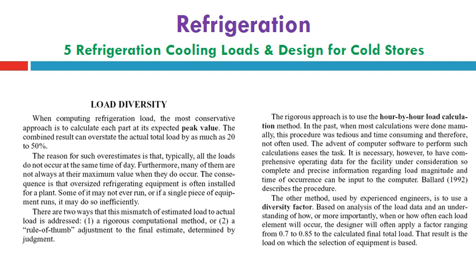Some of it may never run, or if a single piece of equipment runs, it may do so inefficiently. There are two ways that this mismatch of estimated load to actual load is addressed. One, rigorous computational methods. Two, rule of thumb adjustment to the final estimate determined by judgment.